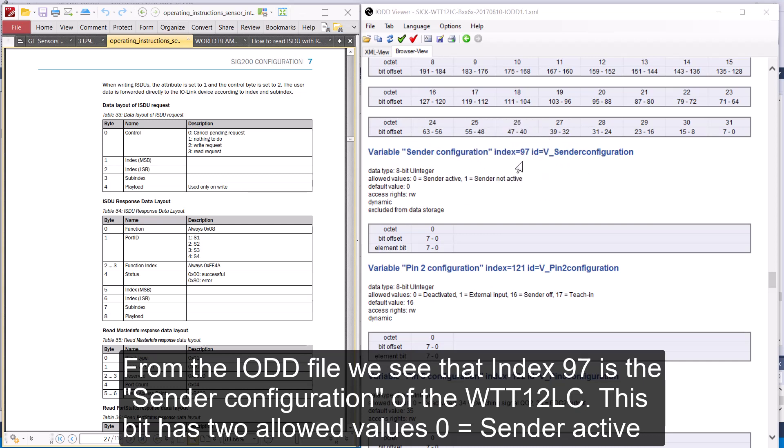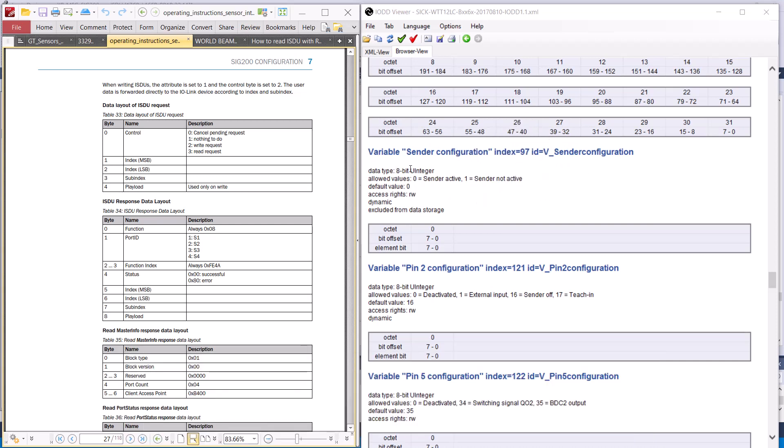From the IO-DD file of the WTT12, we can see that Index 97 is the sender configuration. This has two allowed values: 0 equals sender active or laser on, and 1 equals sender not active or laser off.